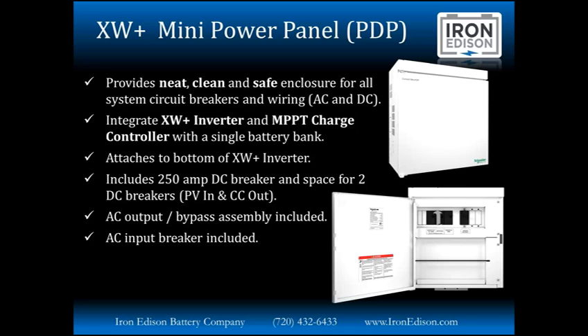In normal operation, you're going to have the inverter powering everything directly. But if for whatever reason you need to take the inverter offline for maintenance, whatever you can think of, you can flip that bypass switch, and the AC input will then bypass the entire inverter system and power your loads directly. So if you have a generator or the grid, whatever is connected to your AC input, if you flip that bypass assembly, whatever's coming in that AC input is going to power your loads directly. The inverter then can be taken offline without taking all your loads down for service or whatever it may be you need to do.